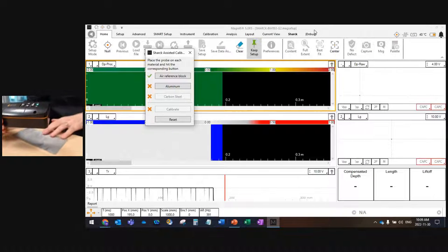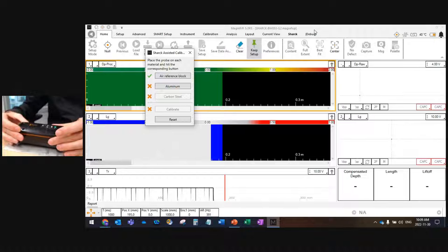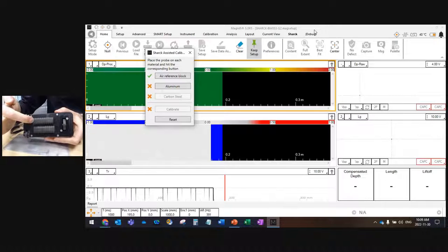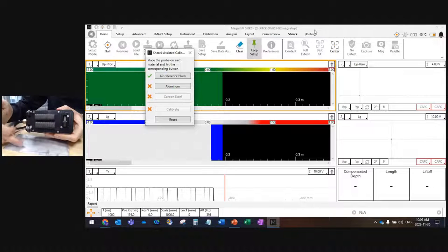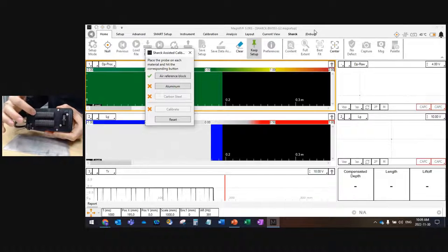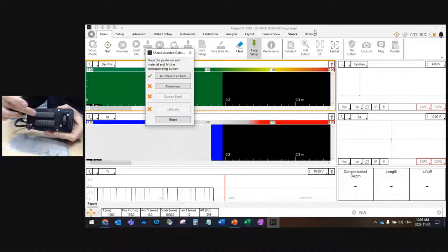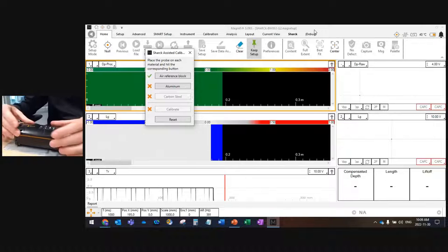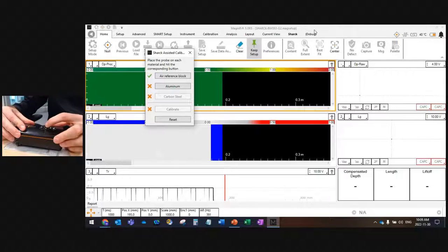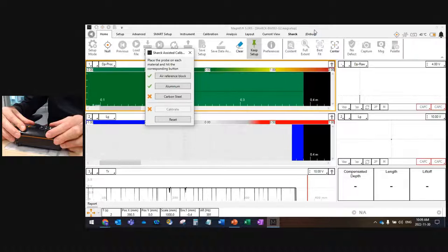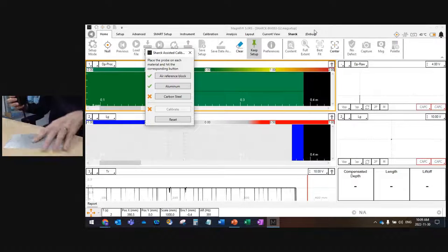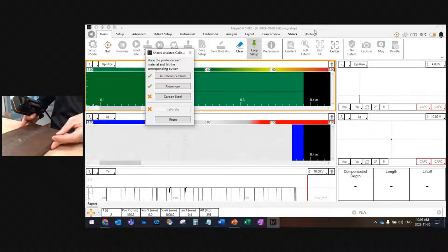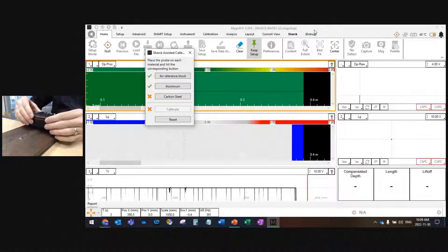Step number two, the aluminum. What this will do here is that every single one of those 22 sensors will sense the aluminum and they will basically be calibrated so that afterward each of them will provide exactly the same value and exactly the same signal. So I set my probe on the aluminum, I hit calibrate once more. It took some data in the aluminum.